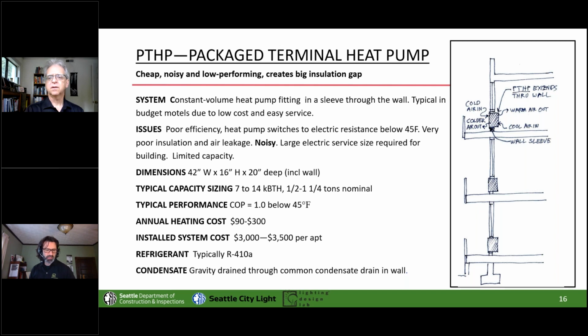It's also worth saying, we commission some of these. That's part of our commissioning, and we always run a camera scope around the bottom. It's hardly ever sealed. You can almost always see light down through the bottom of that seal. Don't know why. It should be sitting there on its weight, but it's really leaky, sometimes to where you can actually feel cold air leaking in that crack. So you can see why I'm not enthused about these.